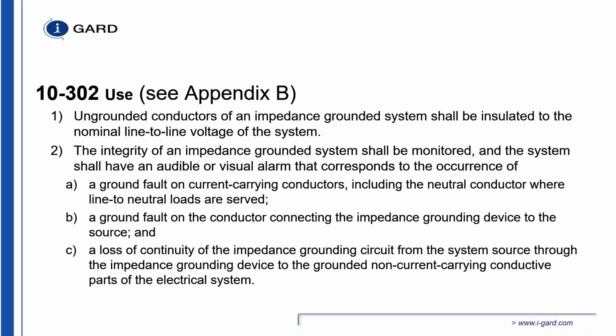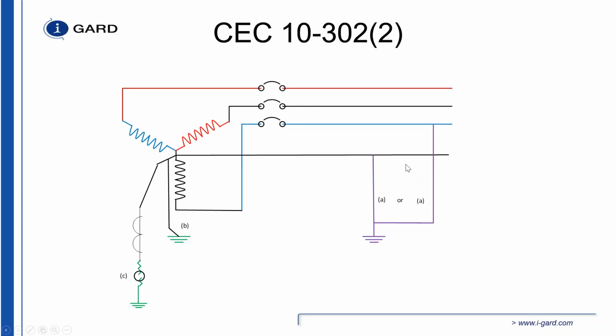A ground fault on the conductors connecting the impedance grounding device to the source has to be monitored, and a loss of continuity of the impedance grounding circuit from the system source through the impedance grounding device to ground. So basically what that means pictorially is we have to monitor if there's a ground fault on the neutral on a resistance grounded system when you have a distributed neutral. You don't have to monitor if there's a ground fault on your neutral if you have a solidly grounded system, which I think will probably cause more harm. And if you saw one of my previous seminars about the benefits of a high resistance grounded system over a solidly grounded system, you'll realize that if you had a ground fault on the neutral of a solidly grounded system, you actually defeat the ground fault protection system. So it is not a requirement on solidly grounded systems, but it is a requirement on impedance grounded systems.